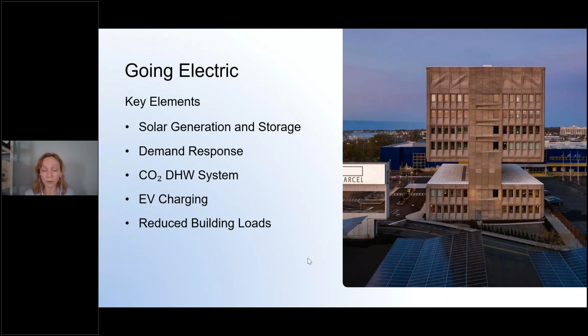To break that down a little more, the CO2 domestic hot water systems—being in your neck of the woods up in the Pacific Northwest, I'm going to guess you're familiar with some of the Sanden, now SanCO2, CO2 refrigerant-based domestic hot water systems. This system is similar, but larger, so it's large enough for commercial buildings, not well suited for domestic use at this point.